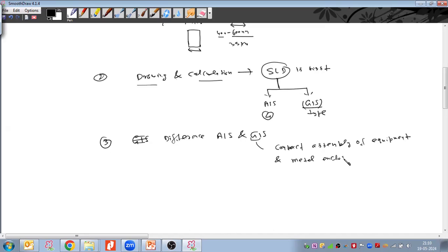That compact assembly of equipment is placed, or installed, in a metal enclosed housing. And which metal do we take? Yesterday we also discussed that we take aluminum alloy, right? So a compact assembly of equipment placed in a metal enclosed, or aluminum alloy enclosed, housing and filled with SF6 gas. This gas also has a pressure. It is compressed gas. On which pressure we compress it, this also we have discussed. And we discussed what the guaranteed leakage rate of the SF6 gas should be as well.